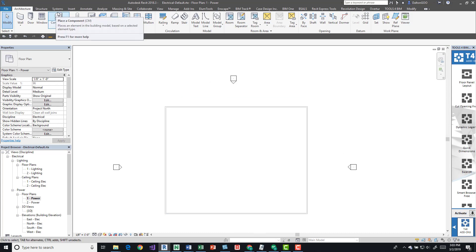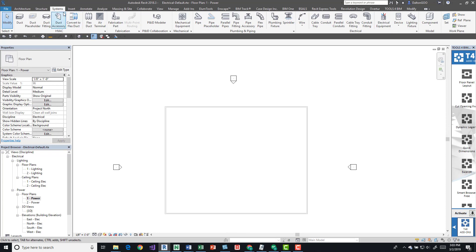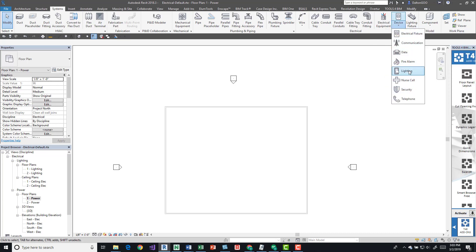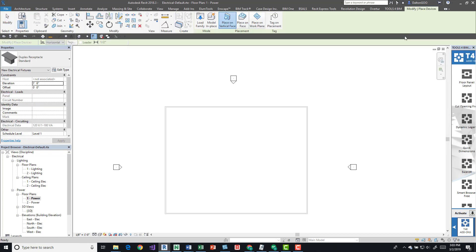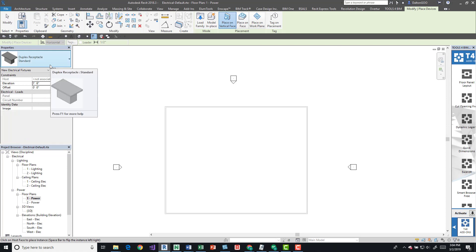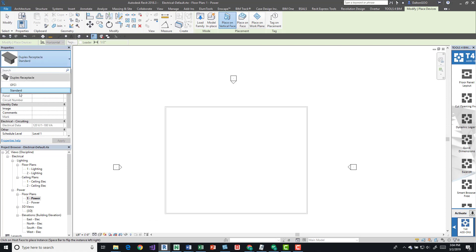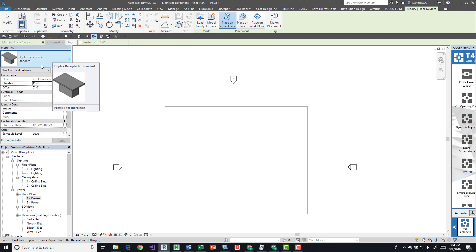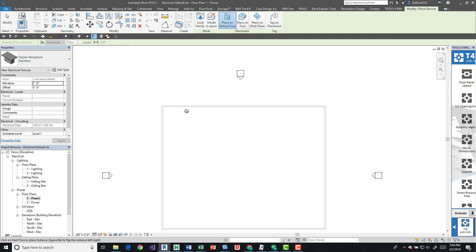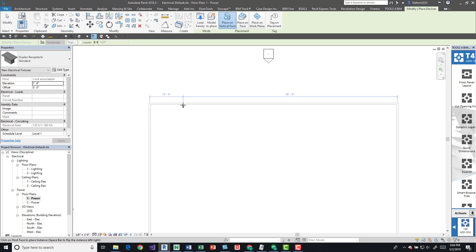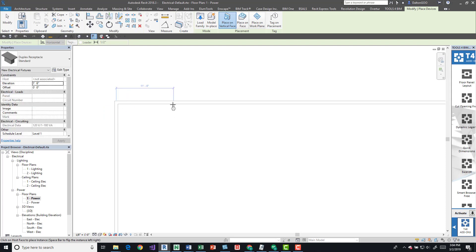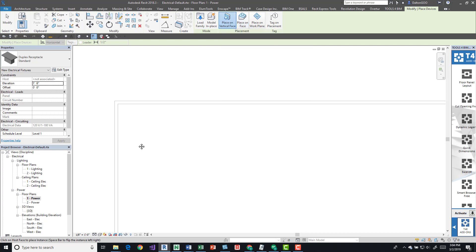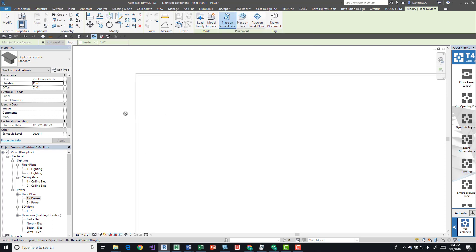For placing outlets, it's pretty simple. If we come to the systems tab on the ribbon, we can come over here to the electrical panel and we've got devices here. We have a number of options: lighting, nurse call, security, electrical fixtures. That's what we're going to focus on. We'll just do a standard duplex receptacle. We can simply come up to a wall and we can place it. We'll get the annotation symbol for our outlets. We can only place on vertical faces such as a wall, because if you come up here to placement, you can see that we are placing on a vertical face.